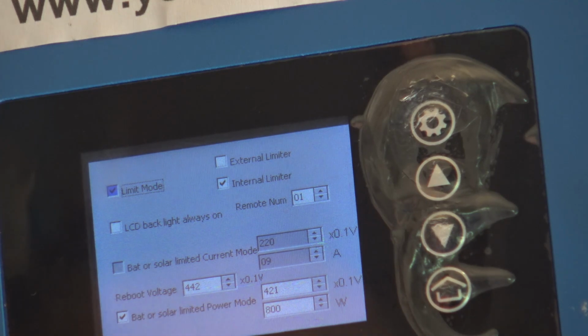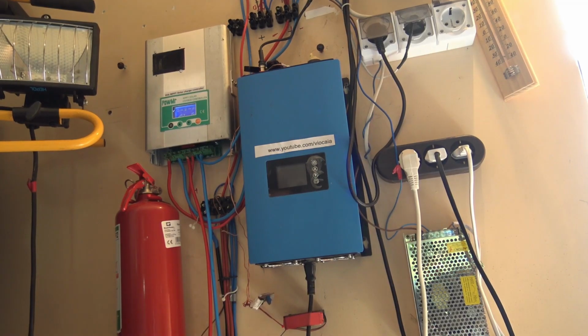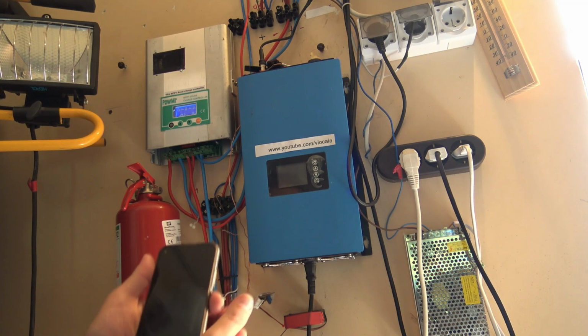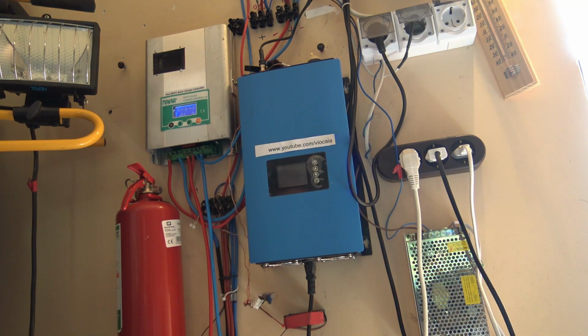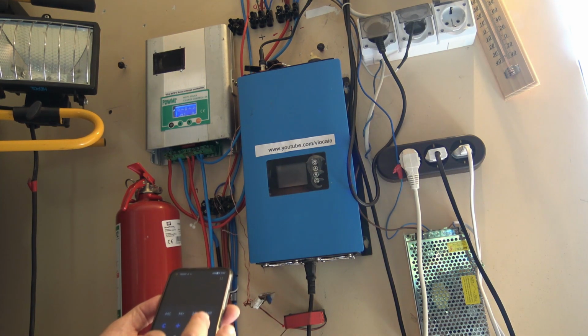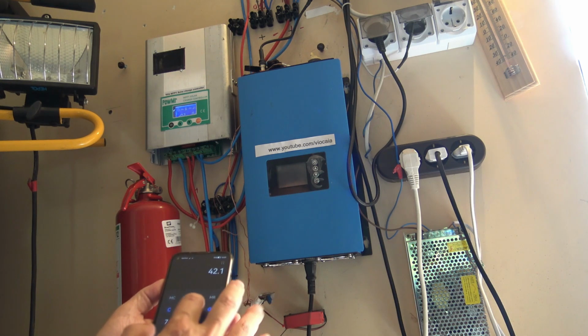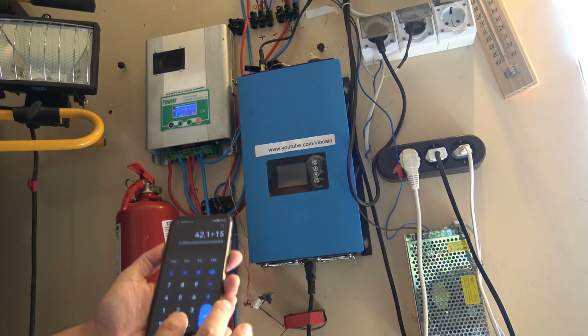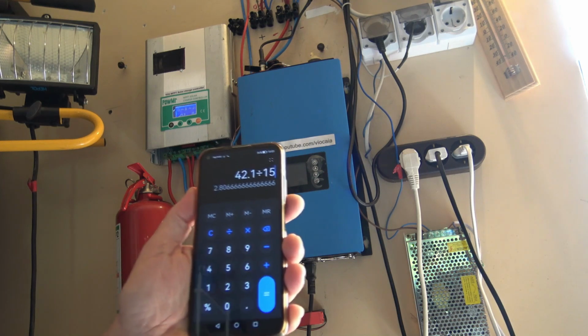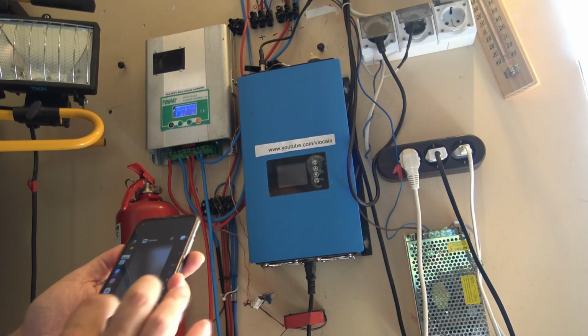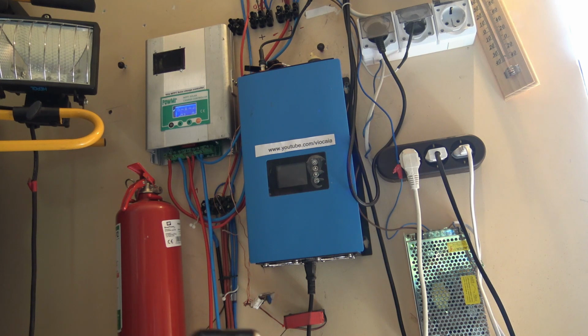It's now set to 42.1 volts, meaning, like I said before, when the batteries reach 42 volts, the inverter will close down. 42.1 volts divided by 15 gives me 2.8 volts of discharge. The range is marvelous, from 4 to 2.8, absolutely okay.